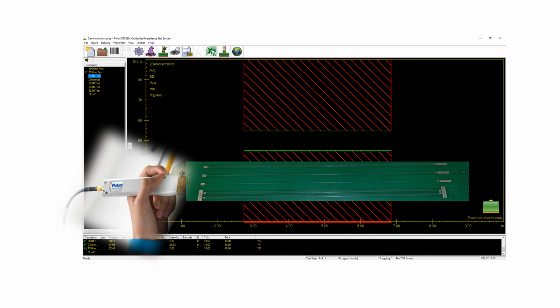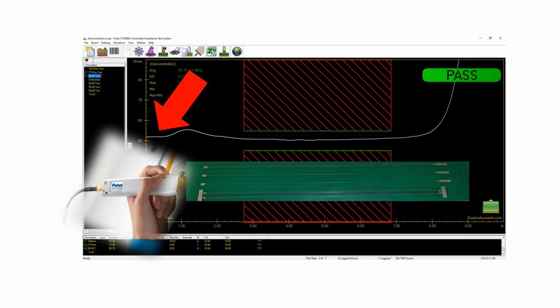I've got the CITS set up here, and what I'm going to do to demonstrate this is, by trickery of laws of physics, slow down the speed of light so you can see the pulse flowing along through the probe and into the coupon and seeing the end of the coupon. So if you watch here at the 50 ohm point, which is looking inside of the probe, and I'll launch the pulse and it'll travel slowly across the screen and up to the open circuit at the end of the coupon. So you can see a bump at the start of the coupon where the launch comes in from the probe, and then a flat area in the center of the coupon, and then the trace rising up to the open circuit at the end.